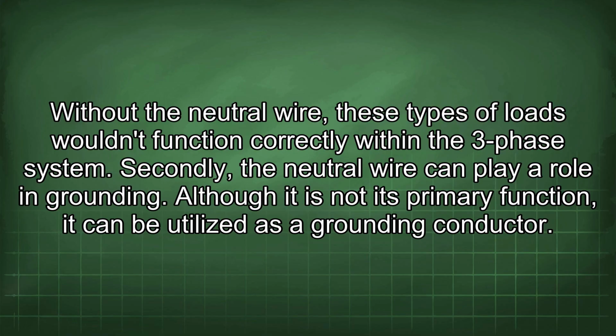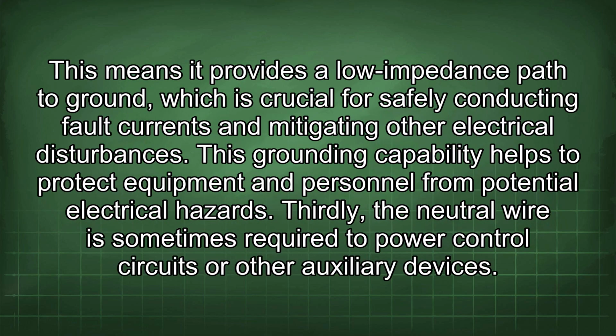Secondly, the neutral wire can play a role in grounding. Although it is not its primary function, it can be utilized as a grounding conductor. This means it provides a low impedance path to ground, which is crucial for safely conducting fault currents and mitigating other electrical disturbances. This grounding capability helps to protect equipment and personnel from potential electrical hazards.